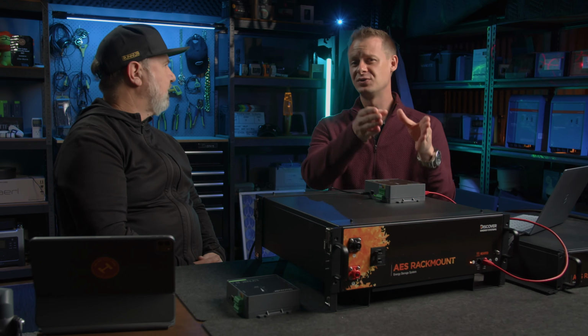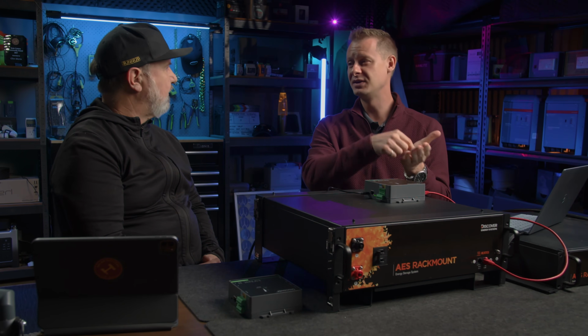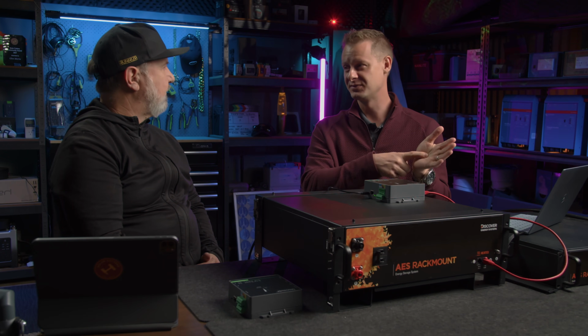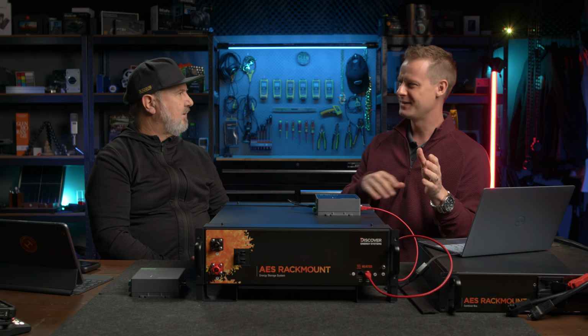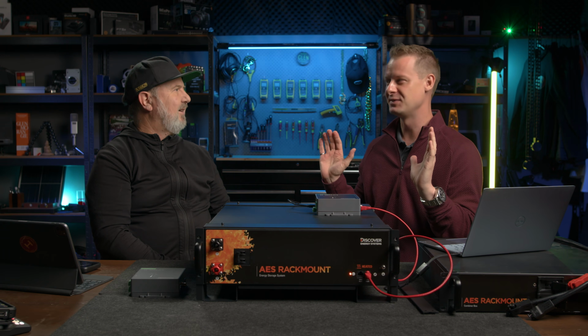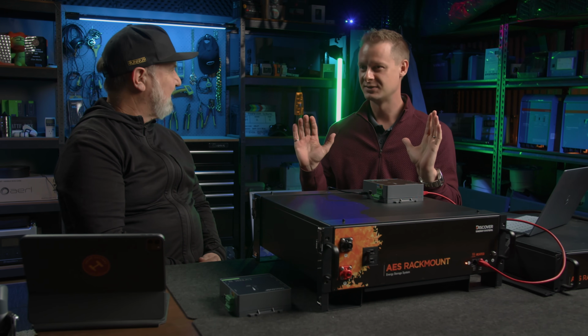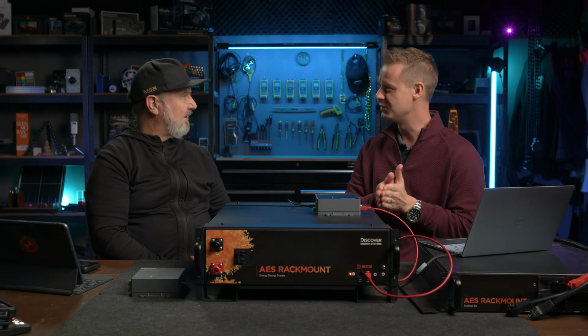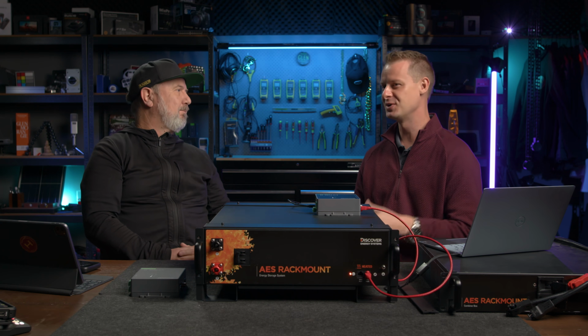The charge controller would say, hey, I'm reading the DC bus and I'm putting out 56 volts. You go to the batteries and they're saying my terminal voltage is only 55. You've got voltage drop on the bus. We were seeing upwards of 1200 millivolt voltage drop. So charge current ground to a halt.